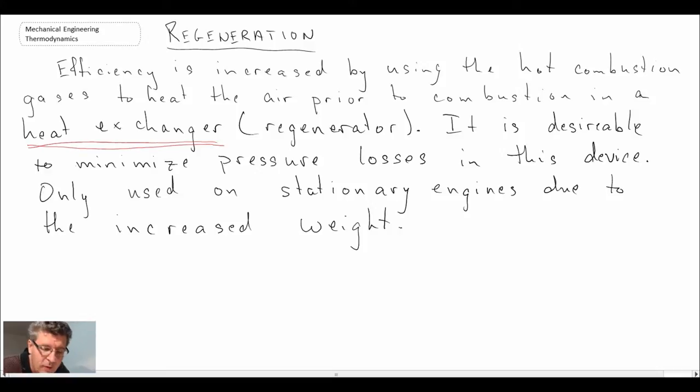The gas would flow through it. In this case, what we're doing is heat exchange - it's a gas to gas heat exchanger, so exhaust gas to compressed air in this particular case. You want to minimize pressure drop in this device because that would be a loss if you have high pressure drop.